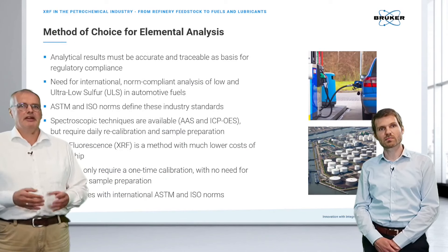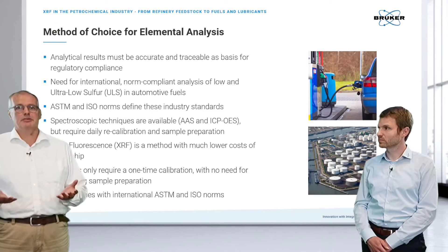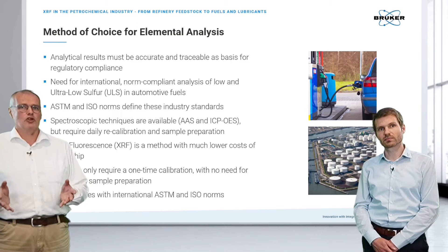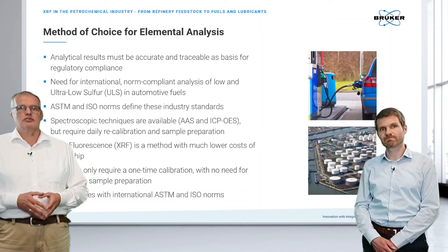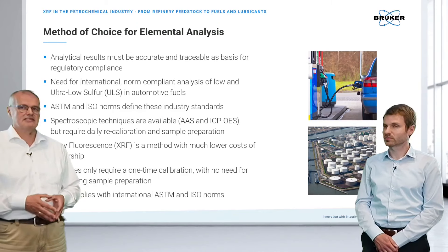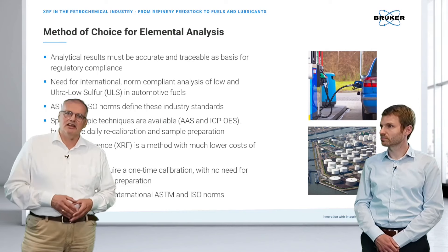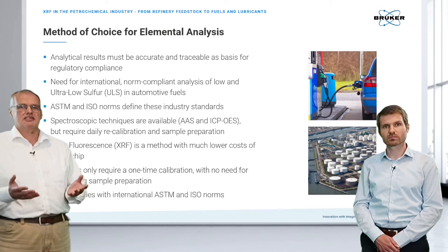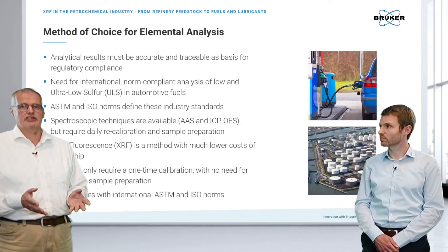There are different analytical methods available. Results must be accurate, traceable, and comparable between process labs and labs along the shipping chain, so they need to be norm-compliant — especially for low and ultra-low sulfur fuels like gasoline. Methods like AAS or ICP-OES are labor and consumable intensive and often require daily recalibration. XRF offers lower cost of ownership with a one-time calibration, minimal sample preparation, and compliance with international norms.